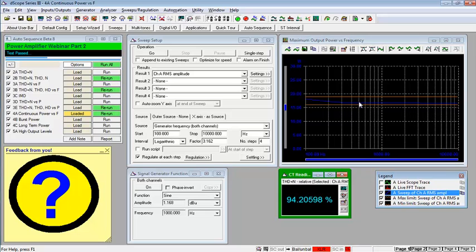I found out what the problem was there, and it's important that you stop and consider what you're measuring and how, and what filters might be being applied to your tests, in order that you ensure that you set them up to give you the answer that you're expecting. The test instrument will give you the result that you've set up, but you need to stop and think about what it is that you're attempting to accomplish before you set the instrument up.